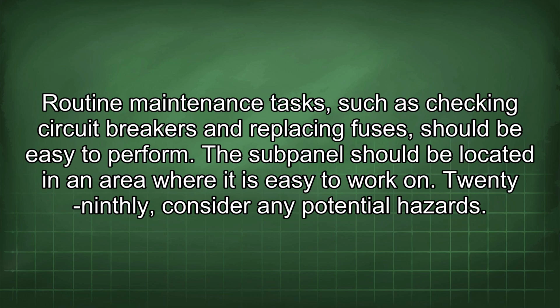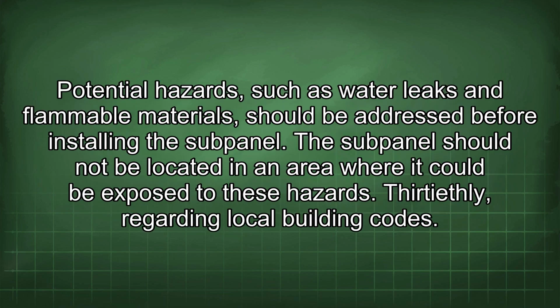28thly, you must think about the maintenance tasks. Routine maintenance tasks such as checking circuit breakers and replacing fuses should be easy to perform. The subpanel should be located in an area where it is easy to work on. 29thly, consider any potential hazards. Potential hazards, such as water leaks and flammable materials, should be addressed before installing the subpanel. The subpanel should not be located in an area where it could be exposed to these hazards.